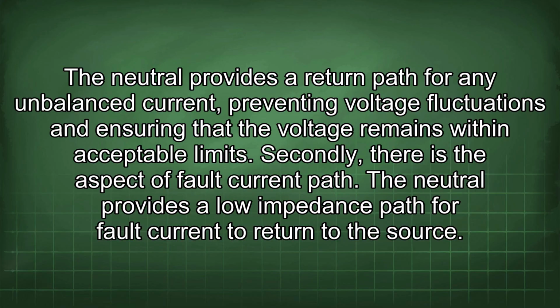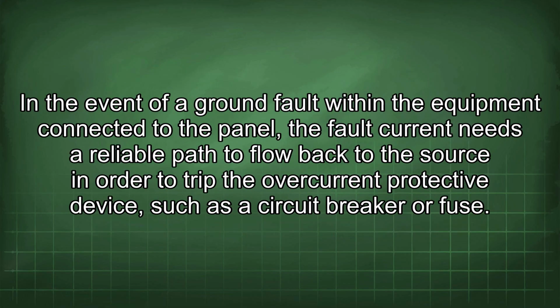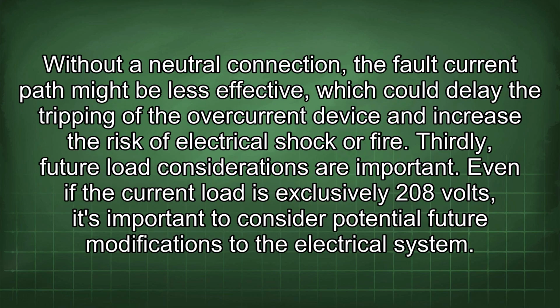acceptable limits. Secondly, there is the aspect of fault current path. The neutral provides a low impedance path for fault current to return to the source. In the event of a ground fault within the equipment connected to the panel, the fault current needs a reliable path to flow back to the source in order to trip the overcurrent protective device such as a circuit breaker or fuse. Without a neutral connection, the fault current path might be less effective, which could delay the tripping of the overcurrent device and increase the risk of electrical shock or fire.